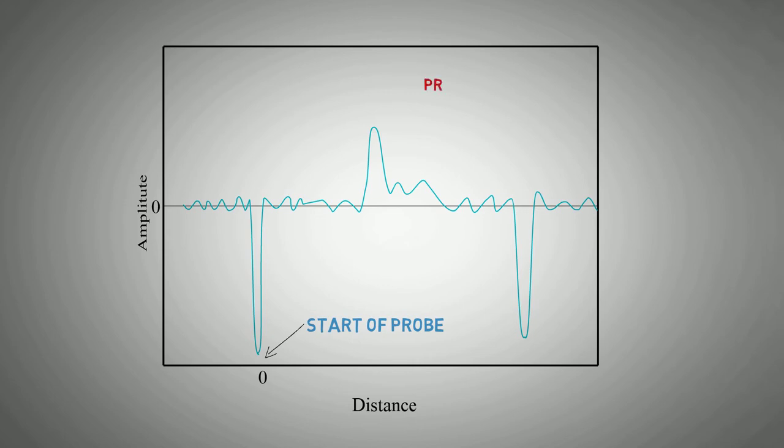The surface of the product will indicate as a positive amplitude that will be positioned depending where the surface of the product is in relation to the probe. Finally, the last negative amplitude will indicate the end of the probe where the reflections drop off.